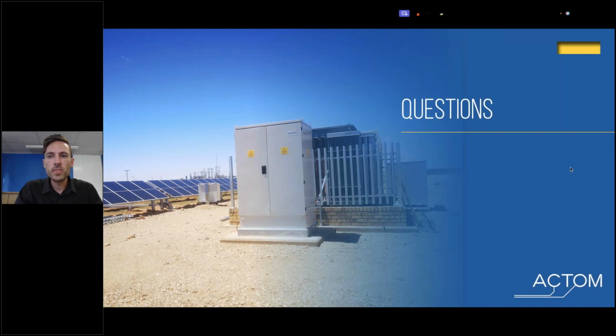Lehlononolo Mulapo asks how does your system differ from the online dissolved gas device, which isolates the transformer automatically upon realizing a gas has risen to a catastrophic level? The gas analyzer will still ultimately have the control. That, and the Buchholz relay, will basically keep the transformer from going totally haywire. But this is more to prevent it getting to that point, so the values we select are a lot more conservative than the ones used to actually cut power to the transformer. It's also important to understand that would just be a dashboard with no analytics behind it - you won't have the historical data and all of that on the back end.